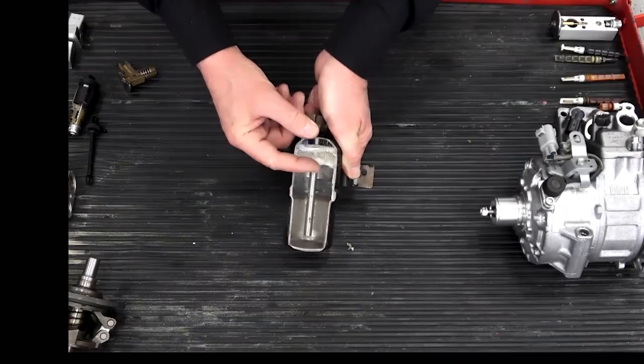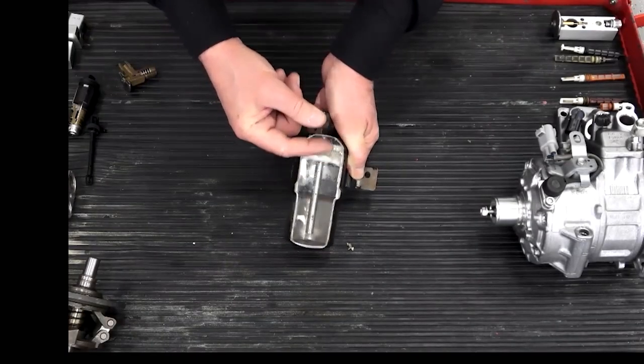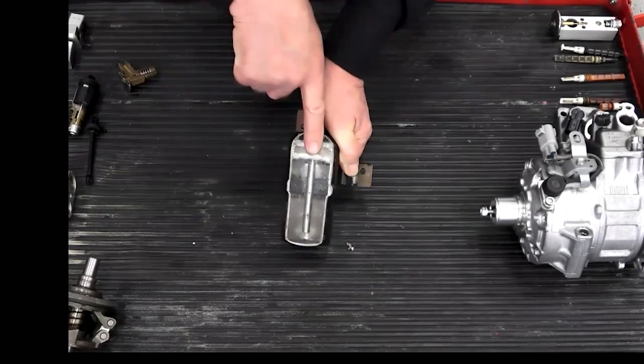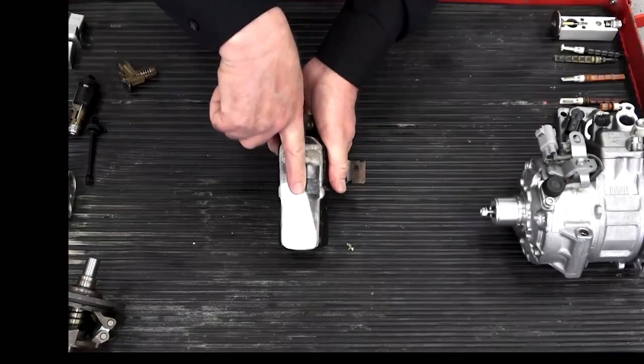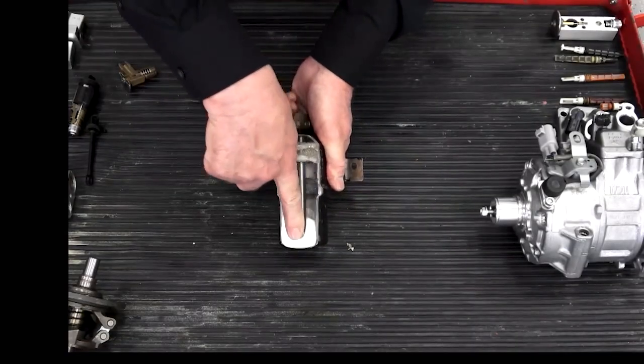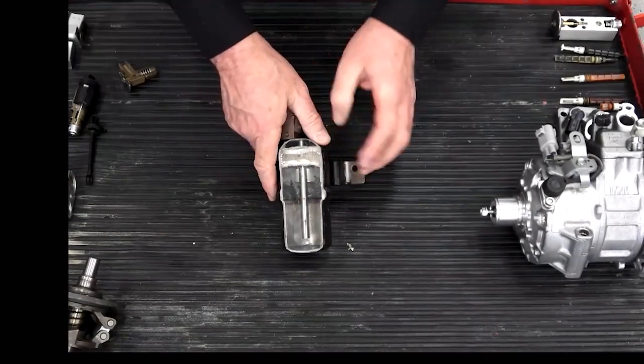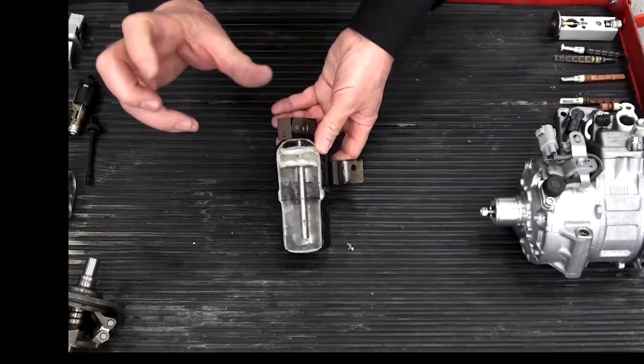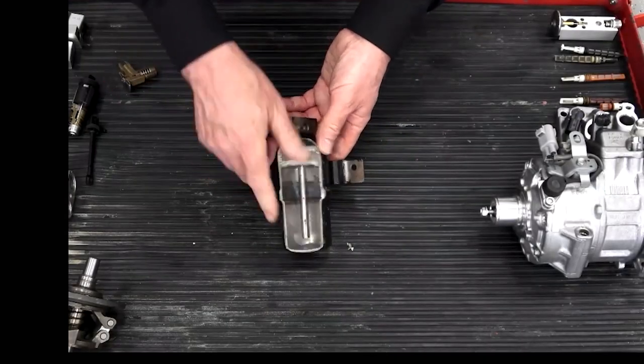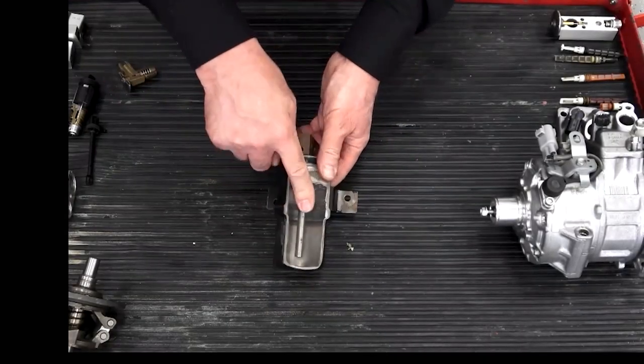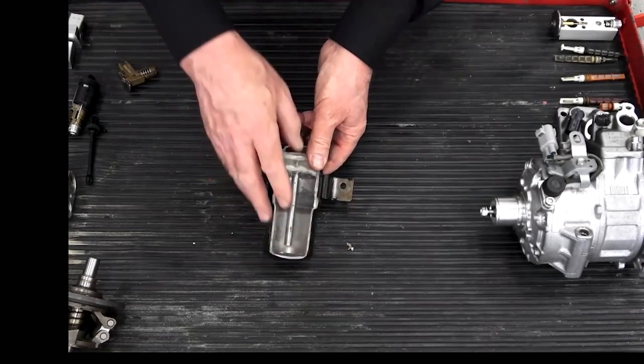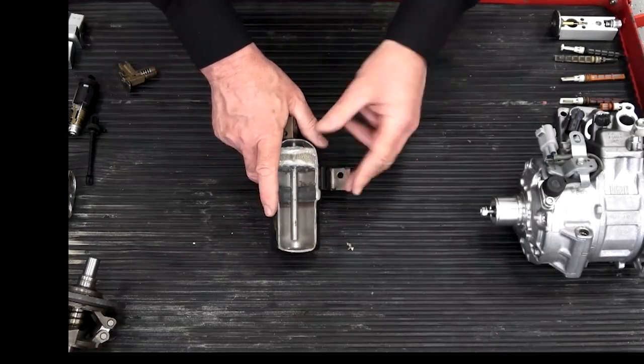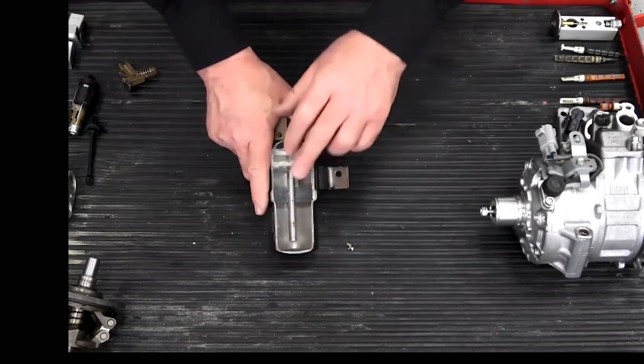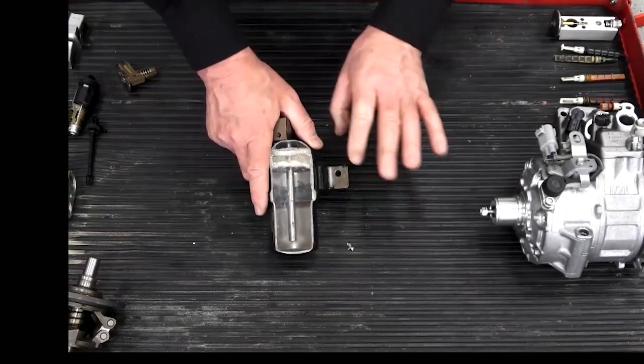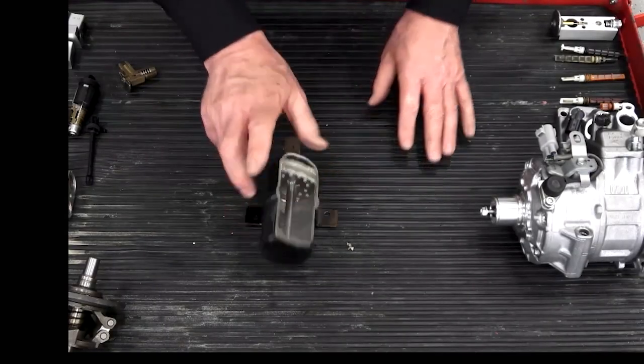The receiver dryer also has a fairly big filter inside to prevent debris getting to the TXV valve. You can see a long pickup tube that's supposed to go almost at the very bottom of the can. And that's the liquid vapor separator function. So it's like an aerosol. It picks up liquid from the bottom of the can. So the receiver dryer acts as a liquid vapor separator, but in reverse to the accumulator, meaning that it ensures that only pure liquid arrives at the TXV valve.